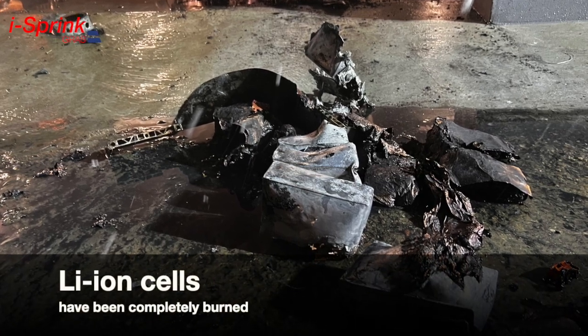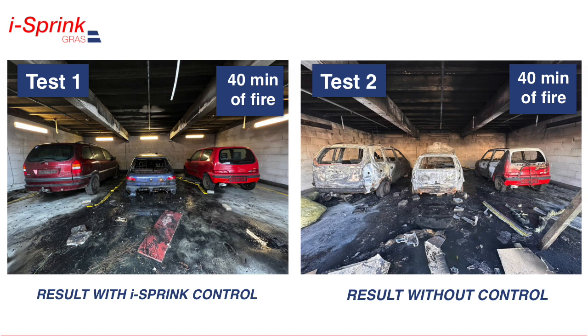The lithium-ion battery cells were completely burnt out. The left photo shows the result of 40 minutes of effective control of an electric vehicle fire in a garage by the i-Sprink system: vehicles in adjacent parking lots remained unaffected, and the facility still has an efficient electrical system and can be used after removing the wreck. In the right photo, the result of an uncontrolled electric vehicle fire in the garage for 40 minutes: all vehicles were completely burned, the electrical installation is damaged, the concrete is detached from the ceiling, and the construction rods are exposed. The facility must be taken out of use.